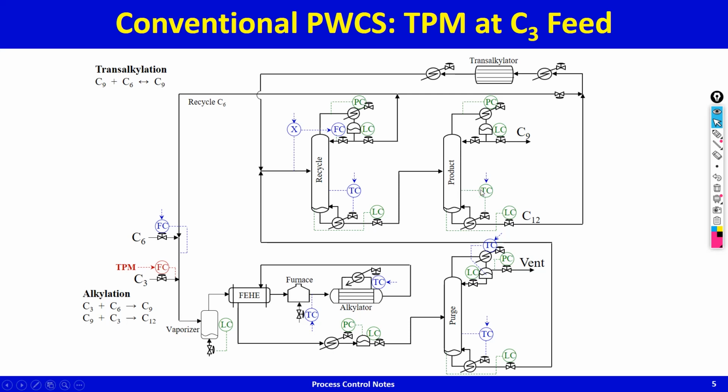However, if you put in a temperature controller, this temperature controller is going to adjust the reboiler duty so that the tray temperature remains fixed, and this loop is going to be fast, because as soon as the reboiler duty changes, vapor boil up changes, therefore tray temperature changes, because more will boil up across all the trays. Vapor flow will change across all the trays immediately. Unlike liquid, vapor doesn't take time to reach from bottom to top, whereas liquid takes time to reach from top to bottom. So this is going to be a fast loop.